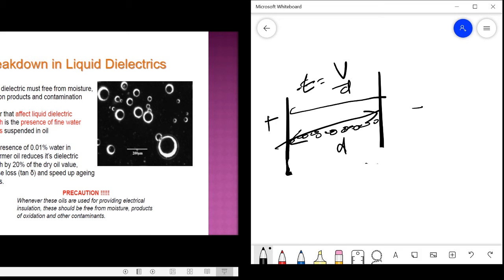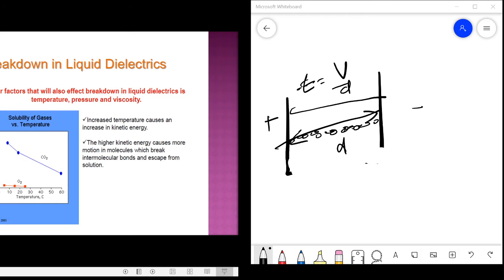Ingat balik, the presence of 0.01% water in transformer oil reduce the dielectric by 20%. Nampak? Hanya 0.01% air dalam transformer boleh reduce 20% of the oil. Precaution: whenever the oil are used for providing electric insulation, it must be free from moisture, products of oxidation and contaminants. Okay, next.